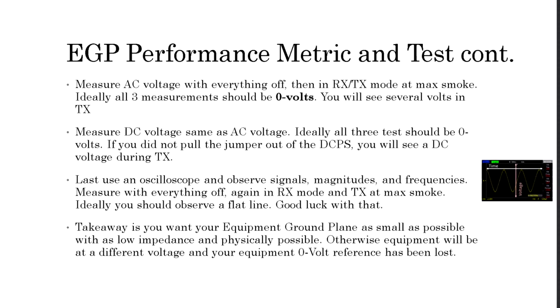The takeaway is you want your equipment ground plane to be as small as possible with as low of an impedance as physically possible. It just makes sense. It's a single wire circuit. Otherwise, equipment's going to all be at different voltage potentials, and you're going to lose your 0 volt reference point.